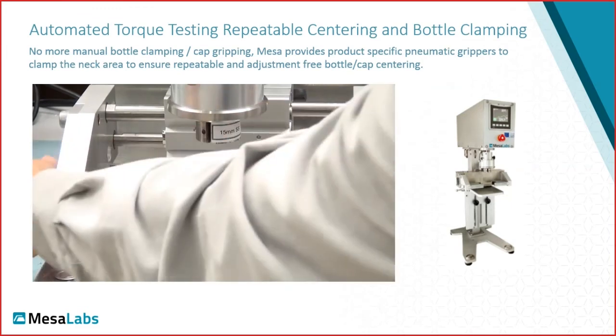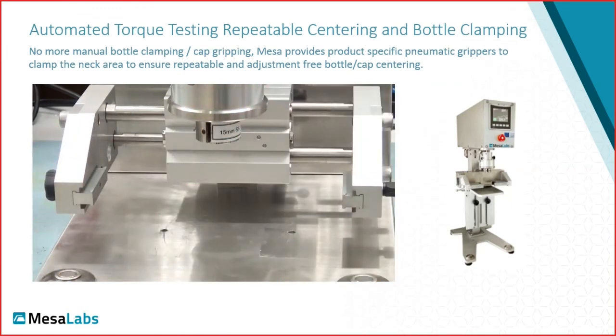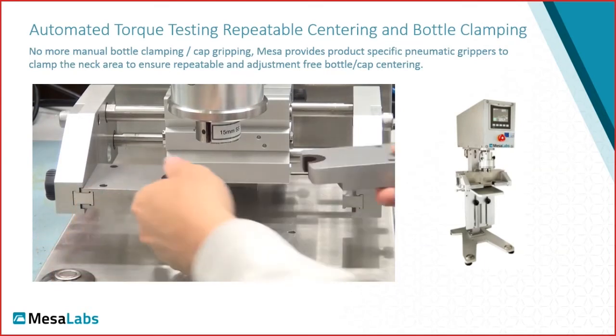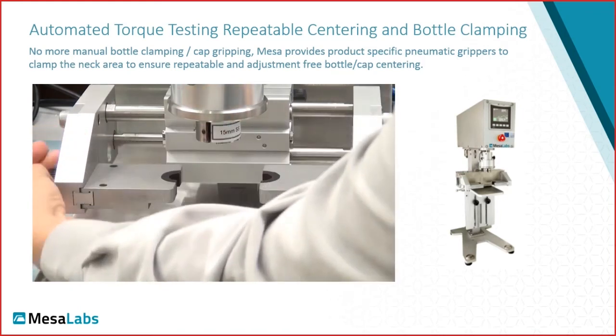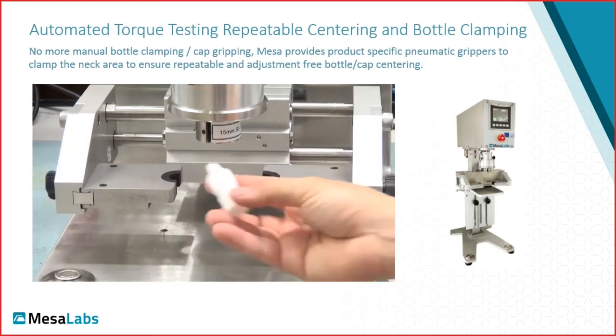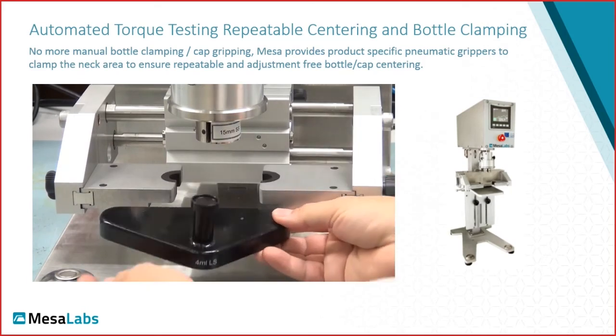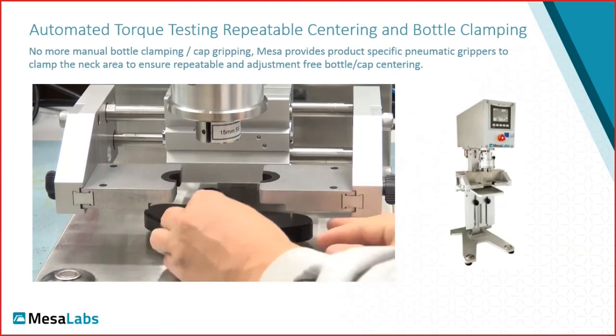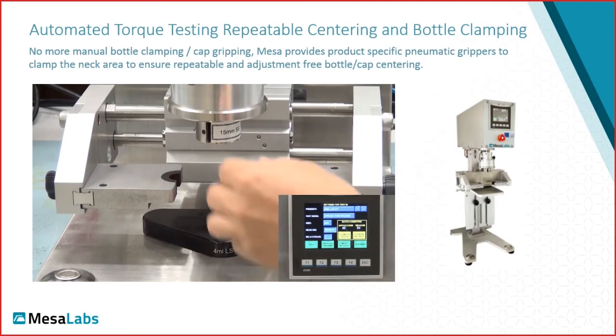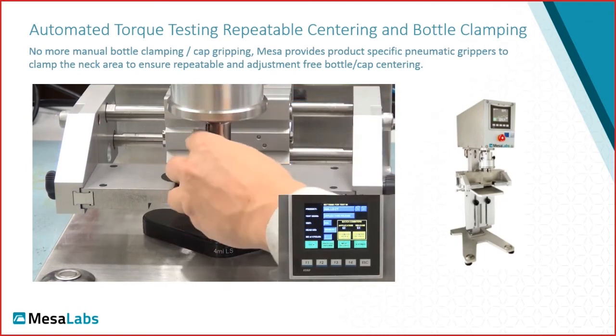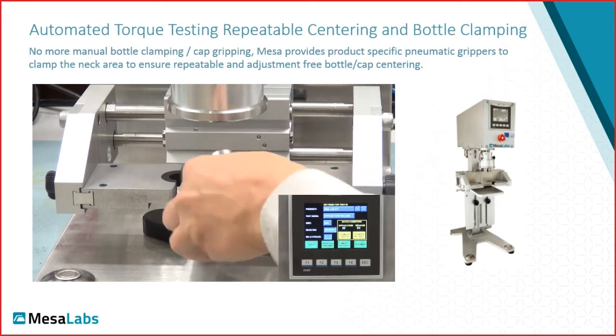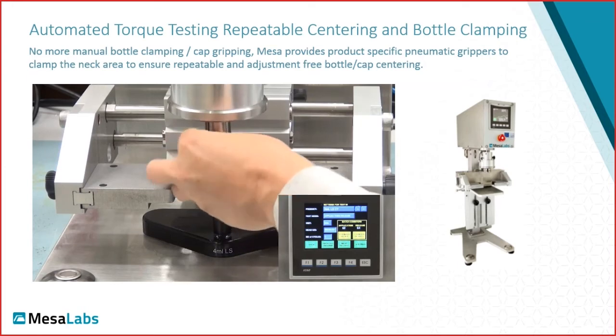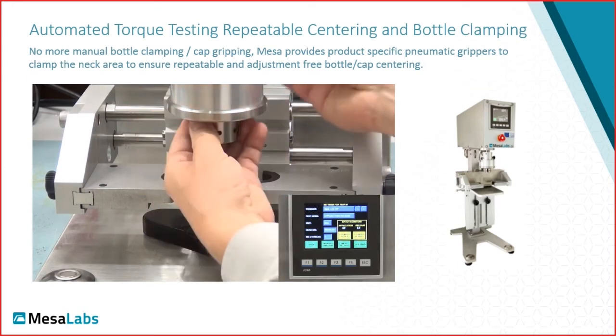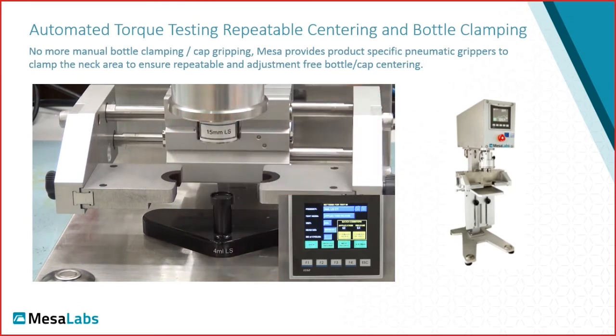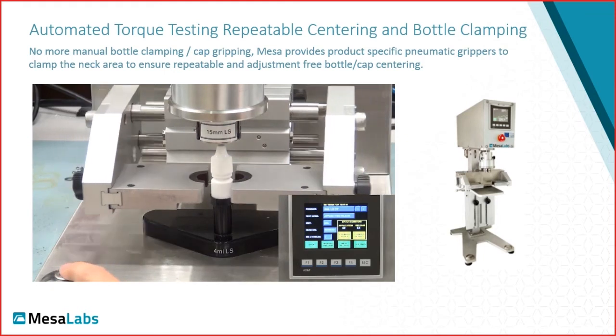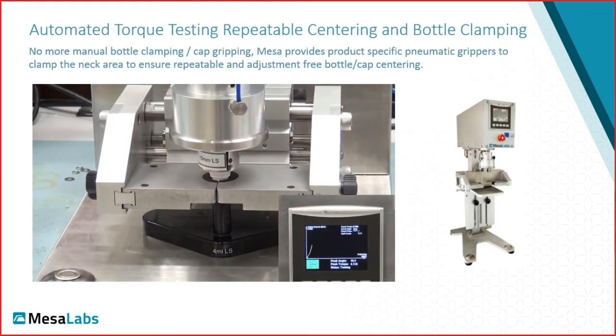That's another benefit of the automated tester. We can automate a number of different operations into one cycle. And then the changeover is as easy as removing those bottle clamps and replacing the cap gripper, replacing the bottle base, and just pressing the 2 push buttons again. This is another base that was coded differently with a magnet, and then the screen shows that it automatically changed to the different test profile. The test profiles can differ in just the acceptable removal torque range, but in some cases, especially if there's a reapplication cycle, the reapplication torque may be different for a smaller bottle, smaller cap, versus a larger bottle and larger cap.